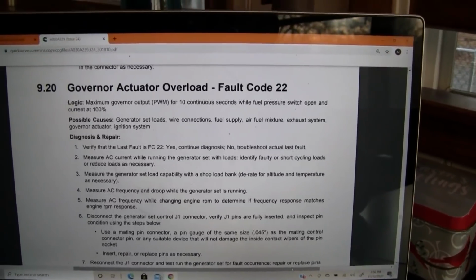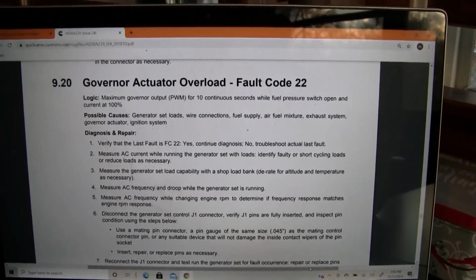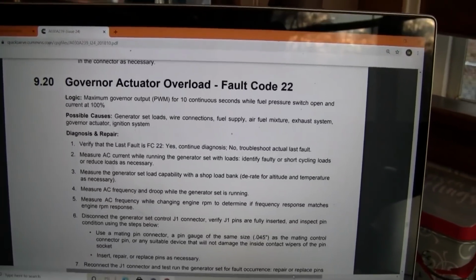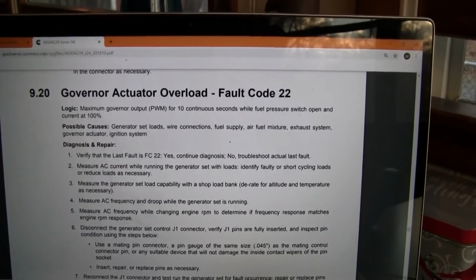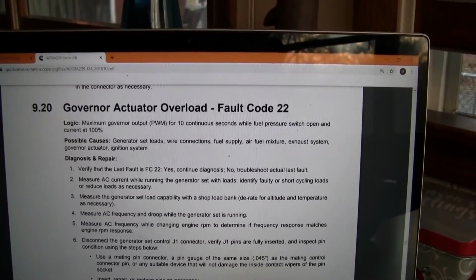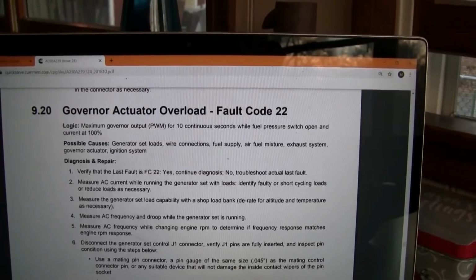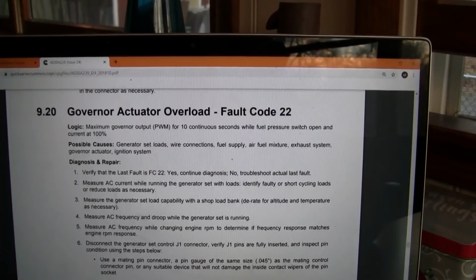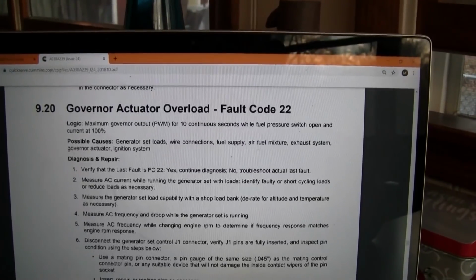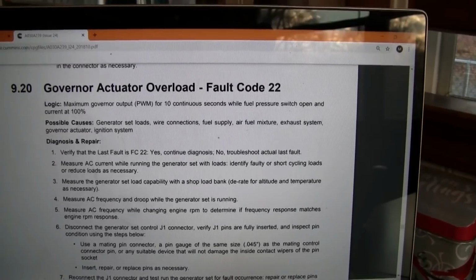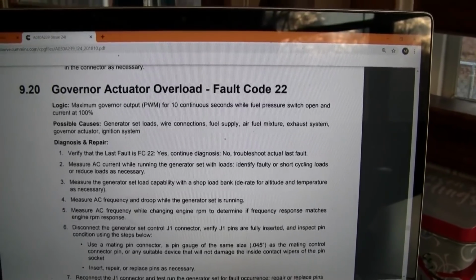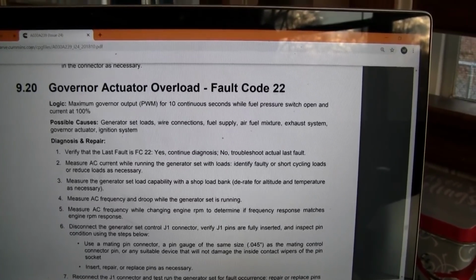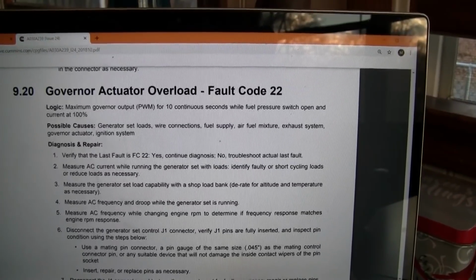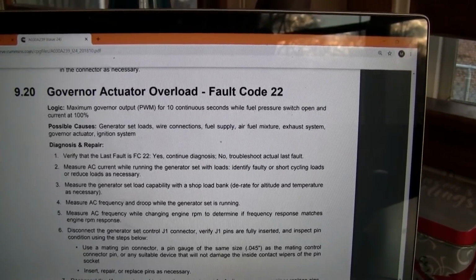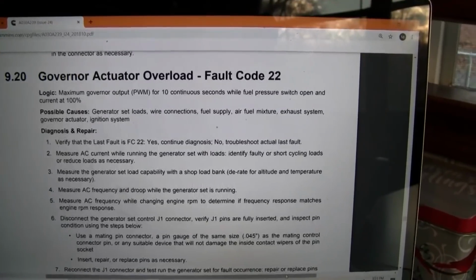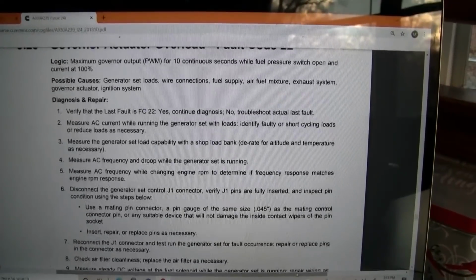15. So here's the manual I pulled up on the Cummins website. So fault 22, governor actuator overload. So we got maximum governor output. It's a pulse width modulated signal for 10 seconds while the fuel pressure switch is open and current is at 100%. Okay, so there's your possible causes. Generator set loads. Certainly if it was overloaded. Wire connections, fuel supply, air fuel mixture, exhaust system, all that stuff. Okay, so you got some diagnostic and repair steps.